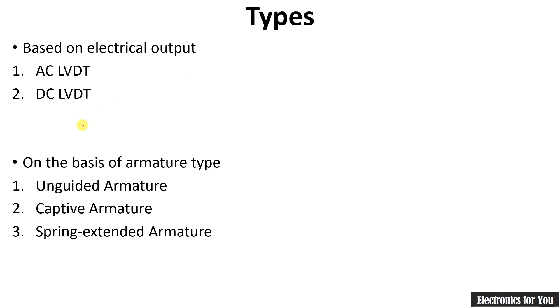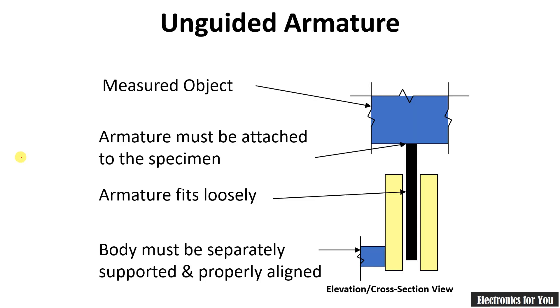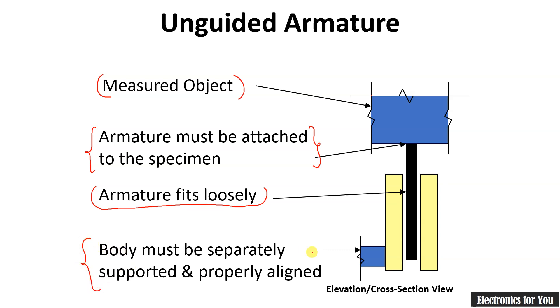Let's see the unguided armature type LVDT first. Here the movable core fits very loosely and no support is provided to the armature — therefore it is called unguided armature type LVDT. The object being measured should be connected to this point. The armature must be attached to the specimen, and the body must be separately supported and properly aligned.